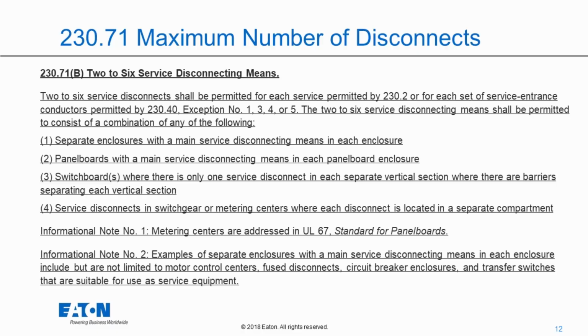Those are needed and are permitted per Article 230 and 230.40. Basically you have four separate conditions. The first one is separate enclosures with a main service disconnecting means in each enclosure.